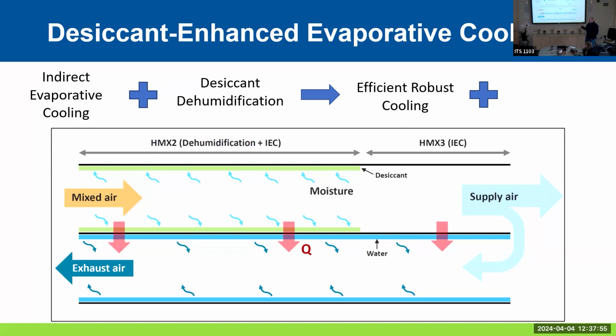So in this system, we're not running any kind of compressors. We are just running fans and pumps. So that's not a whole lot of energy usage and it ends up being a very efficient system. Now, like I said, over time, the desiccant's going to lose its effectiveness. It's going to get diluted and lose its effectiveness, so it needs to be regenerated. Now, that doesn't have to happen in the real time of the system running. It can be done during lower loads, so you can have a very nice and easy load shifting energy storage.